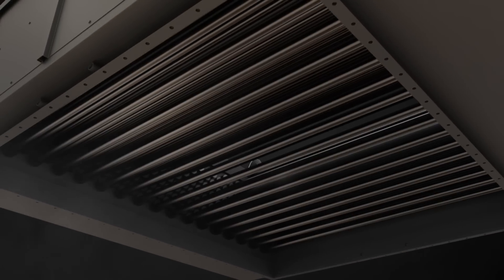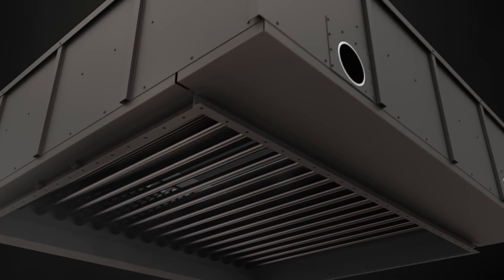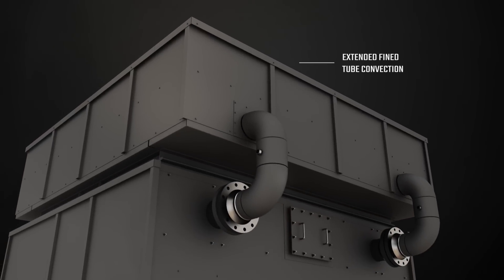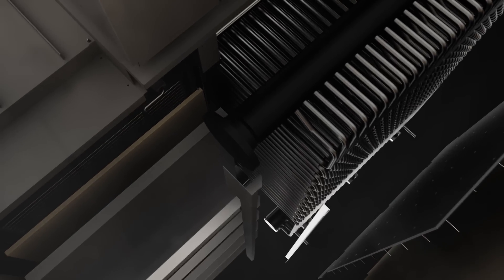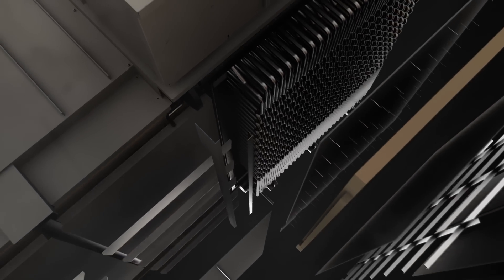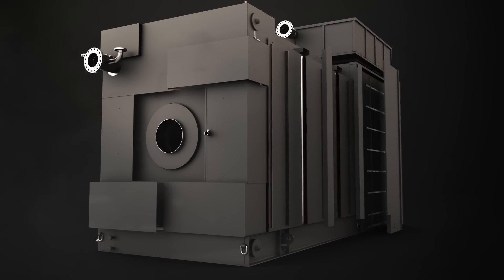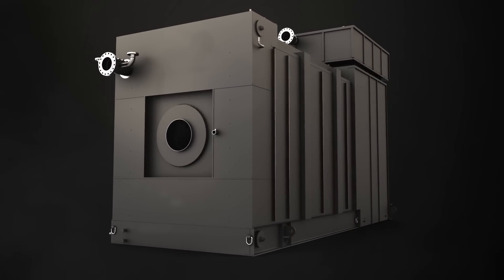The convection is made of two retractable components that conveniently slide out for maintenance and quick turnaround repair. An extended finned tube convection is on top, improving the unit efficiency up to 3% over conventional designs. Heavy duty gas-tight inner casing has been tested at 10 inches of H2O. High quality thick insulation helps reduce radiation losses.